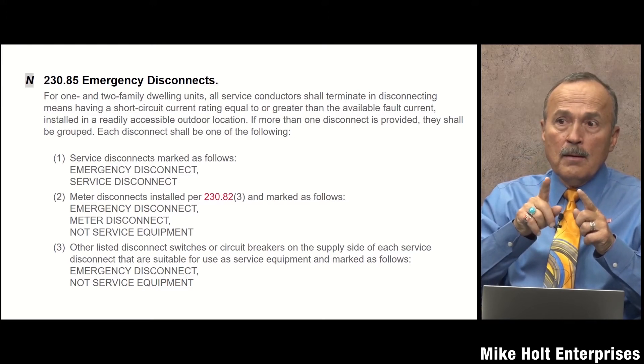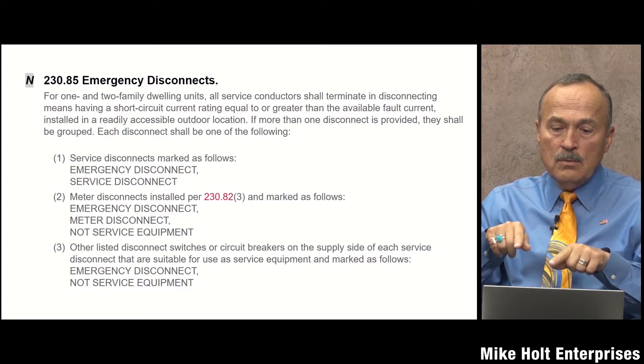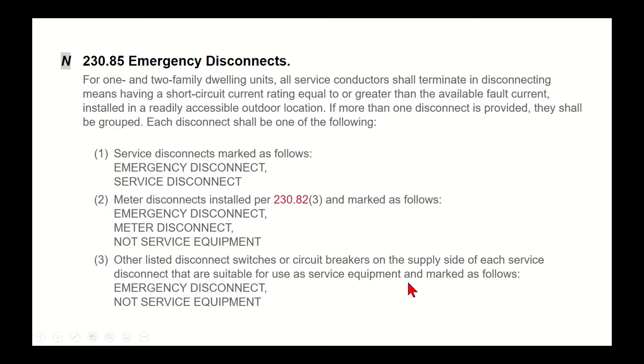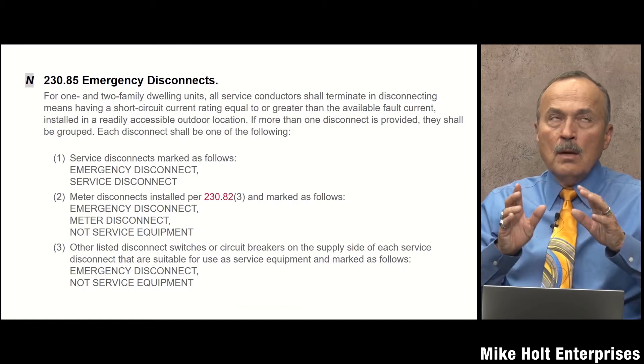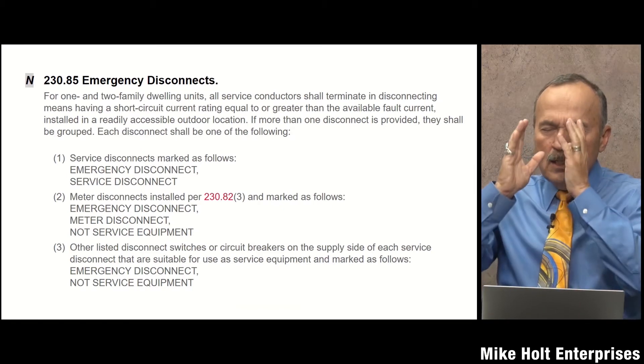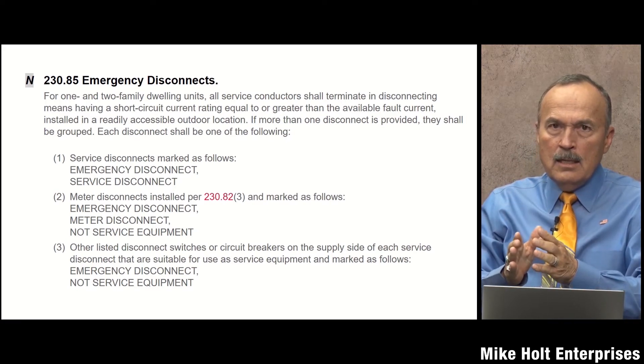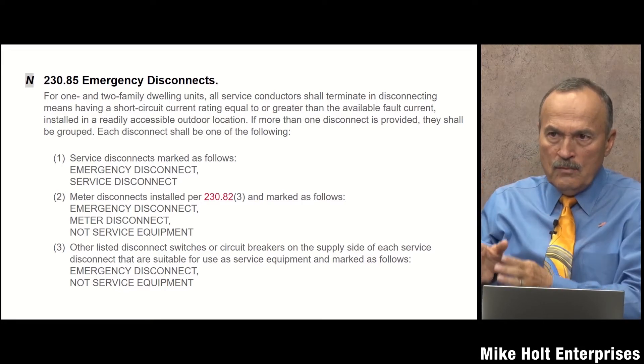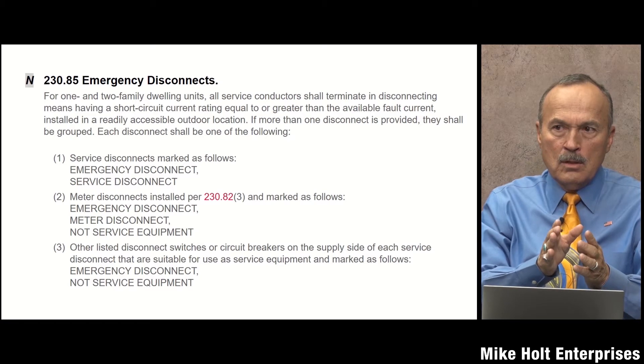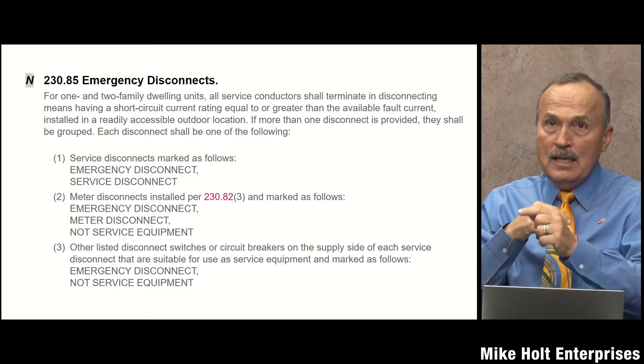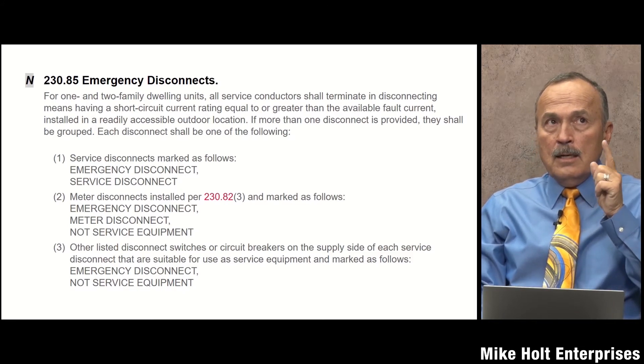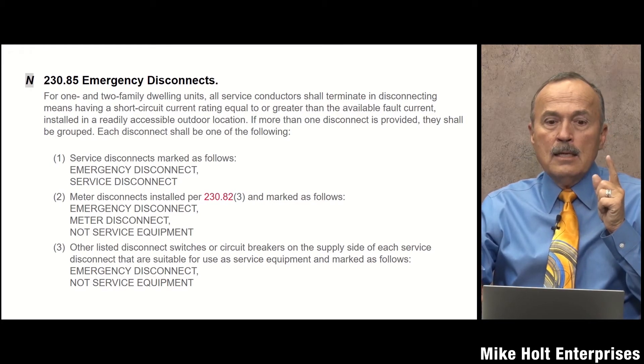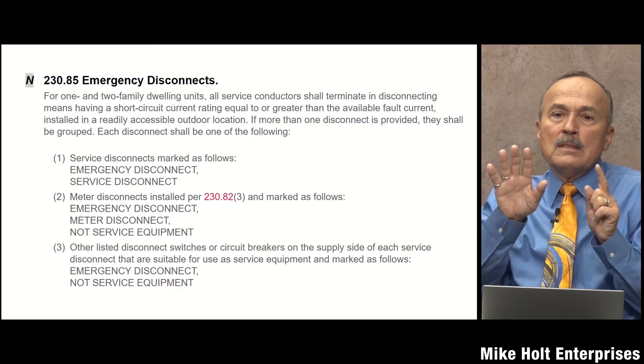That option doesn't require a short-circuit withstand rating — number three didn't say anything about withstand current rating. You can put a listed disconnect, which could be a circuit breaker, on the supply side of each service disconnecting means that's suitable for use as service equipment. So you can get a service-rated disconnect, put it on the supply side of the service disconnect, after the meter — a service-disconnect disconnect.